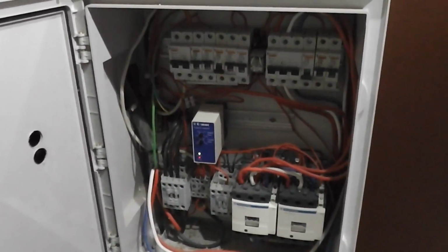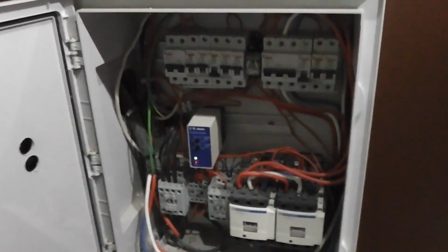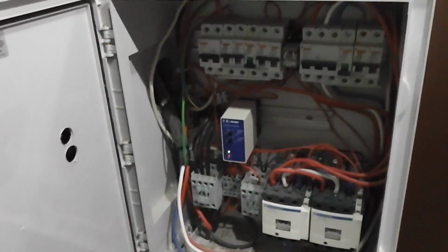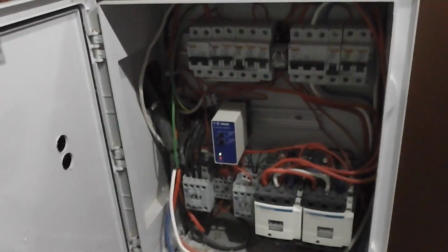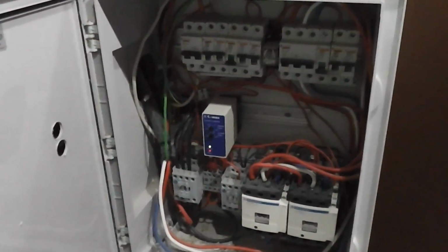There we go - the house is now back on the mains and the generator is idling. It will sit out there idling for 5 minutes just in case the power goes off again. It's already running, so it just revs up and plugs itself back in. But after 5 minutes, if the power is still on, it'll shut itself down and go back to standby.